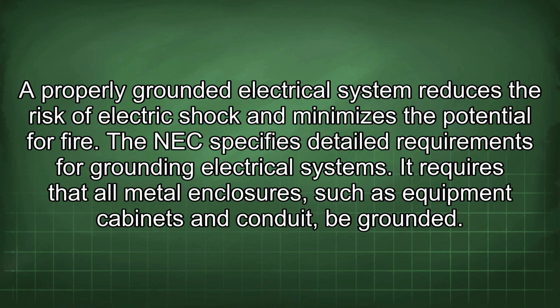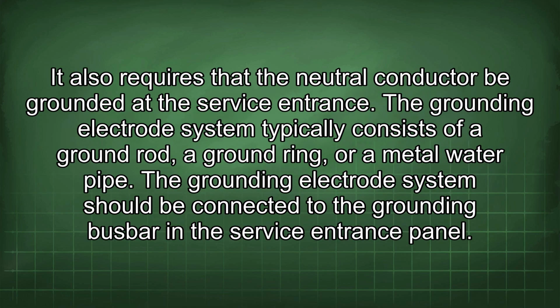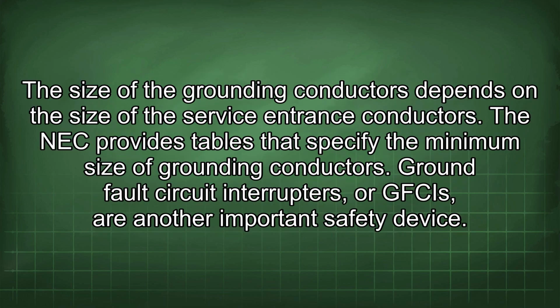It requires that all metal enclosures, such as equipment cabinets and conduit, be grounded. It also requires that the neutral conductor be grounded at the service entrance. The grounding electrode system typically consists of a ground rod, a ground ring, or a metal water pipe. The grounding electrode system should be connected to the grounding busbar in the service entrance panel. The size of the grounding conductors depends on the size of the service entrance conductors. The NEC provides tables that specify the minimum size of grounding conductors.